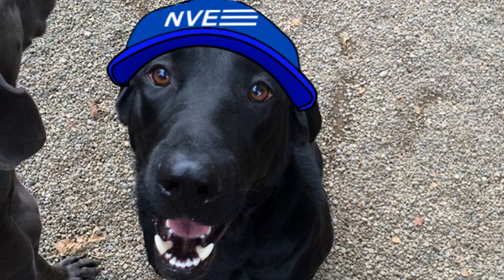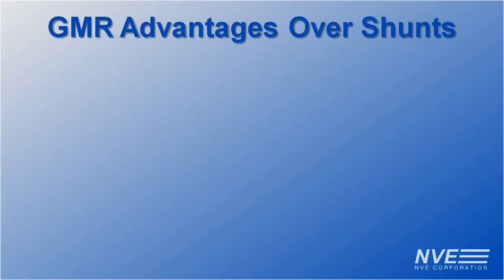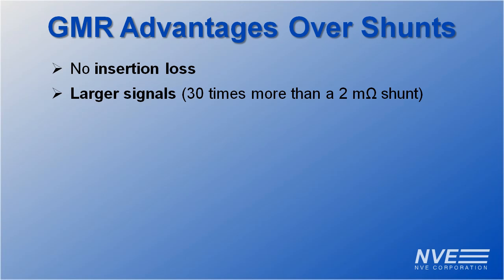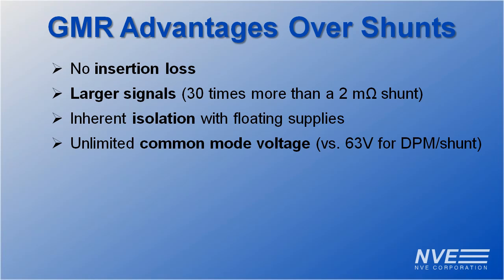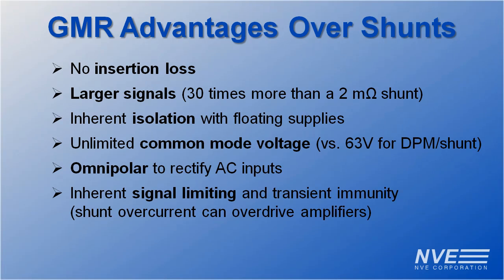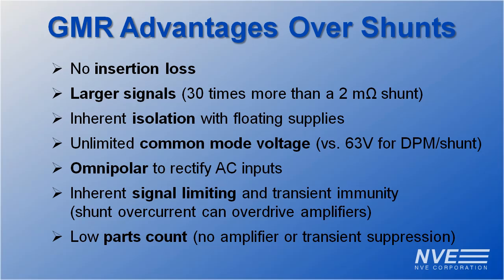So the lab results are in. GMR sensors are ideal for use with DPMs. There's no insertion loss and therefore no self-heating or thermal errors. They have much larger signals than a shunt and don't require an amplifier or transient suppression. There's inherent isolation and therefore unlimited common-mode voltage. They inherently rectify AC signals. And the sensors have inherent signal limiting and transient immunity, which can minimize parts count.